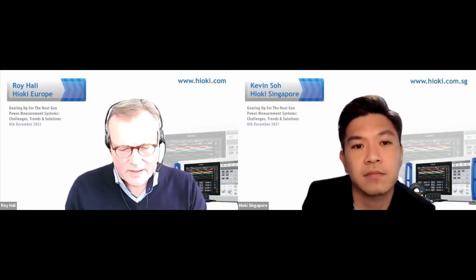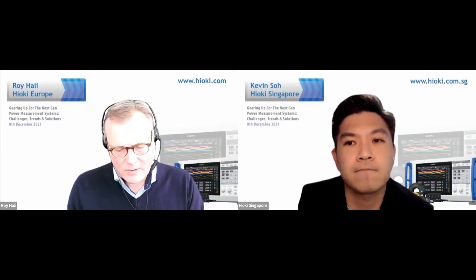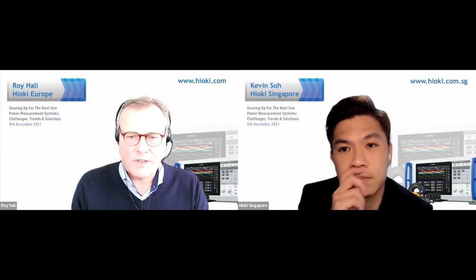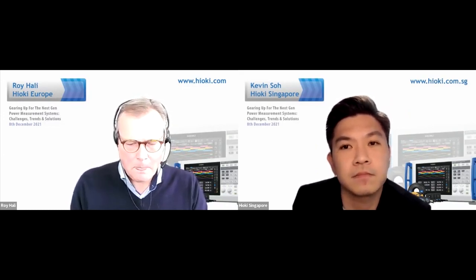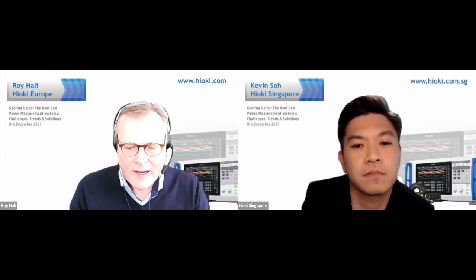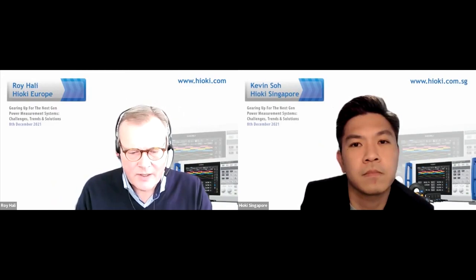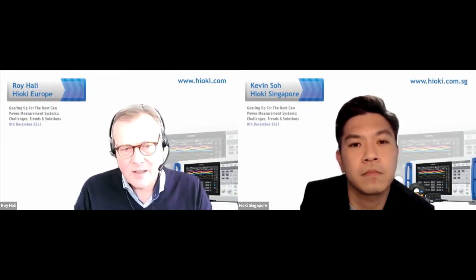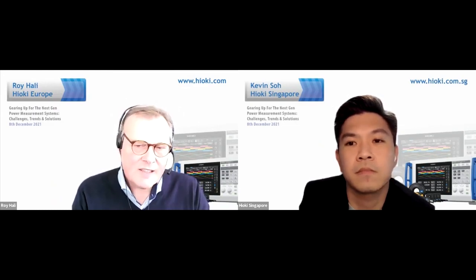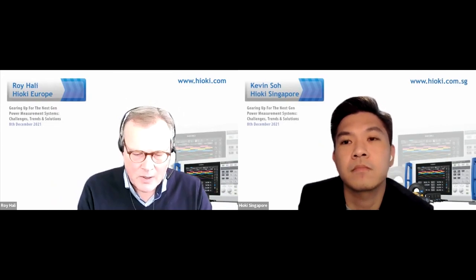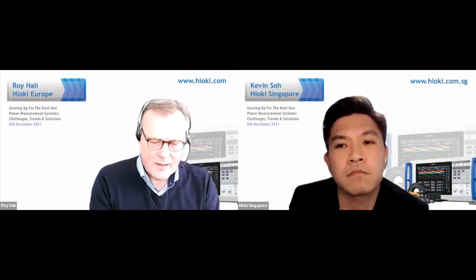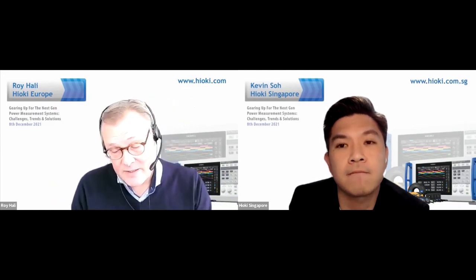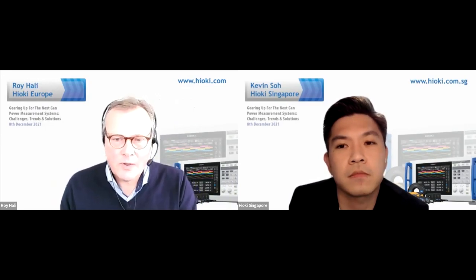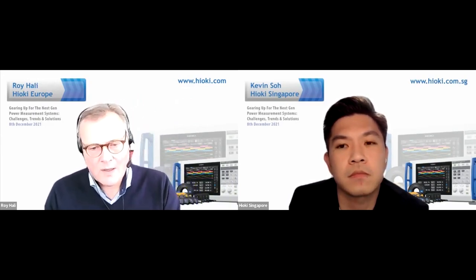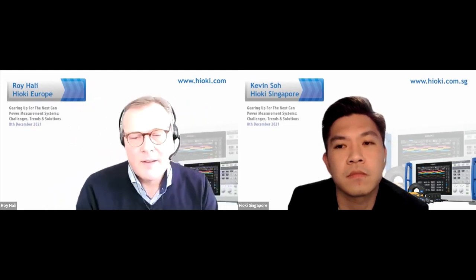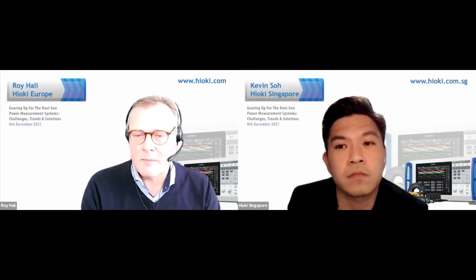If I understand correctly, they are measuring on the battery side. They're measuring the DC voltage of the drivetrains. So in that measurement, it's not necessary to have high bandwidth, and an input module accuracy of 0.07% is already good enough to measure your DC voltage or DC power accurately. By just selecting this input module, you also get an excellent measurement, and it has an effect on the total cost of your test system, because the input module, the U7001, is considerably lower priced than the U7005 with its high bandwidth and high sampling range.